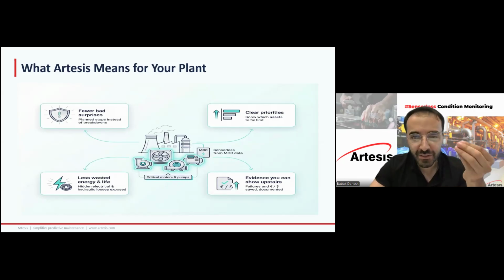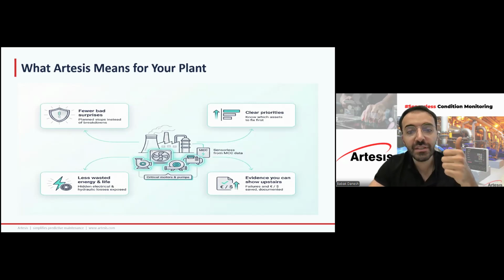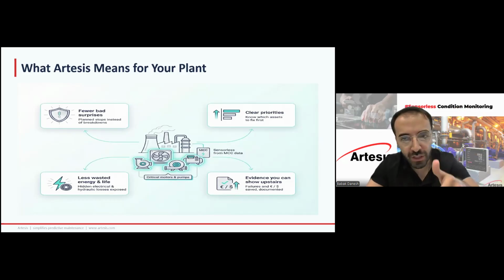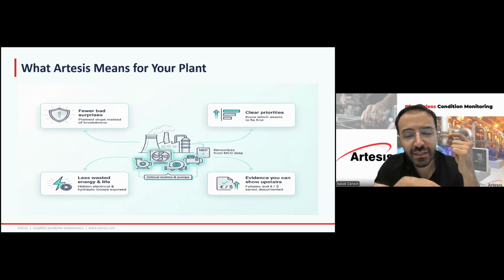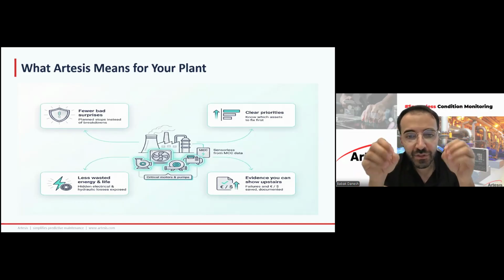For electrical faults, Artesis's strongest model, Professor Ahmet Duyar's model-based fault diagnosis, learns the digital twin of the motor, predicts what current should flow for the measured voltage, and watches how the model parameters change and drift over time. Training shows this model coefficient drift is the main indicator for stator winding faults, rotor-related internal electrical change, insulation-related problems, and other motor internal electrical faults. So a key differentiator is that Artesis separates internal faults.